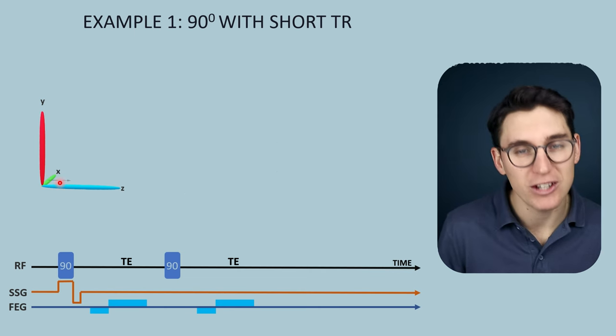In gradient echo pulse sequence diagrams, an alpha symbol is used to indicate that varying flip angles can be set. In spin echo imaging, larger flip angles are generally used, but not always 90 degrees — and in gradient echo, much smaller flip angles are used because of this short TR.